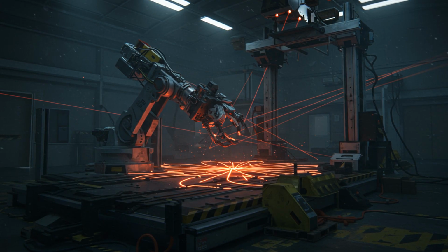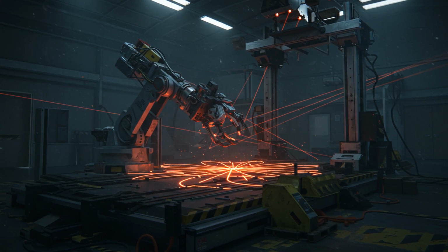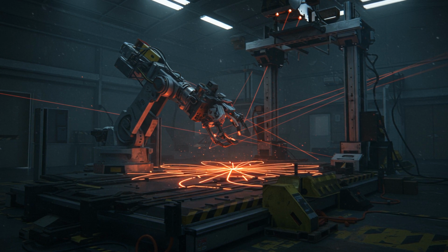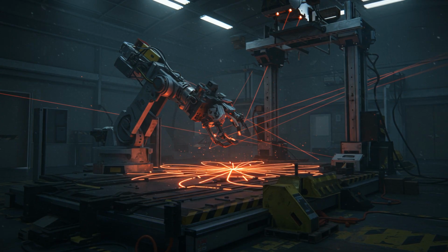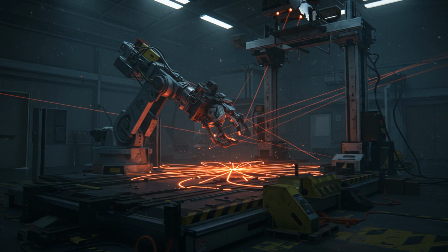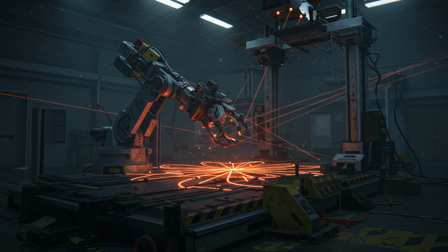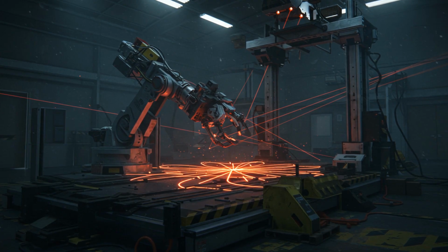Every individual joint is put through a burn-in process, moving continuously for hundreds of hours to ensure there are no manufacturing defects in the motors or harmonic drives. Laser interferometers, tools that use light waves to measure distance, are used to verify that when the robot is told to move 10 microns, it moves exactly 10 microns. Engineers also perform electromagnetic interference tests to ensure the robot won't be affected by other equipment in the hospital, like MRI machines or cell phones.